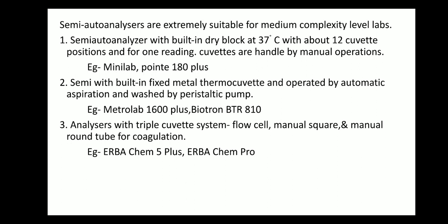Then one more type of semi auto analyzer has a metal thermo cuvette. This is operated by automatic aspiration and washed by a peristaltic pump.